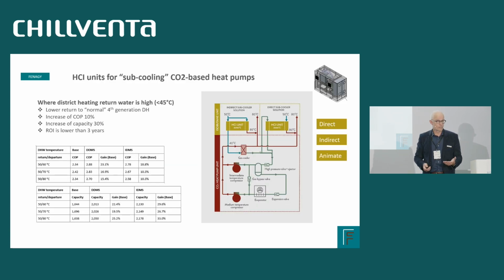What do we do if we don't have cold return? We can add mechanical subcooling. I will just explain briefly. We add an additional heat pump here. It could be our isobutane heat pump. This is 50 degrees return, which is probably a reasonable level in Europe. It's very high in Denmark, reasonable level in Europe. But we add an isobutane heat pump here. We cool down the return, and we heat some of the water to 80 degrees. Now the CO2 heat pump has 40 degrees instead of 50, which is really nice temperature for the CO2 heat pump. And then we are heating water to 80 with the CO2 heat pump. So basically the isobutane as a mechanical subcooler is helping the CO2 heat pump to get back in the game on COP and efficiency. We only have 30 seconds left.